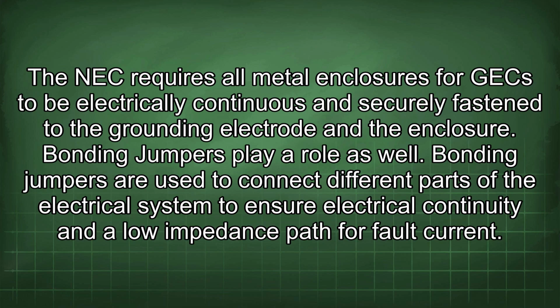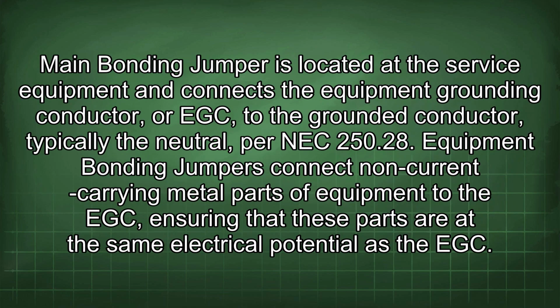Bonding jumpers are used to connect different parts of the electrical system to ensure electrical continuity and a low impedance path for fault current. Main bonding jumper is located at the service equipment and connects the equipment grounding conductor, or EGC, to the grounded conductor, typically the neutral, per NEC 250.28. Equipment bonding jumpers connect non-current carrying metal parts of equipment to the EGC, ensuring that these parts are at the same electrical potential as the EGC.